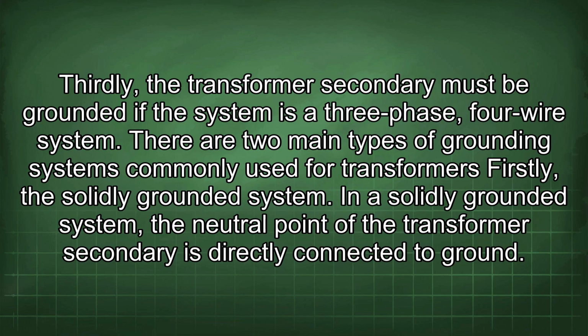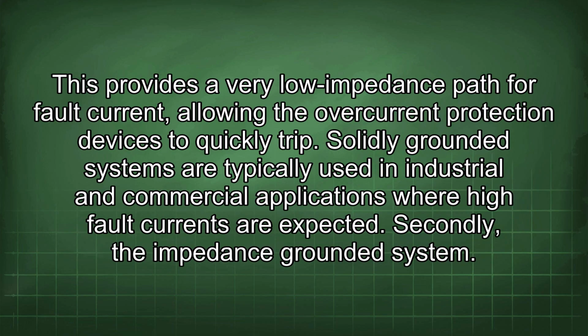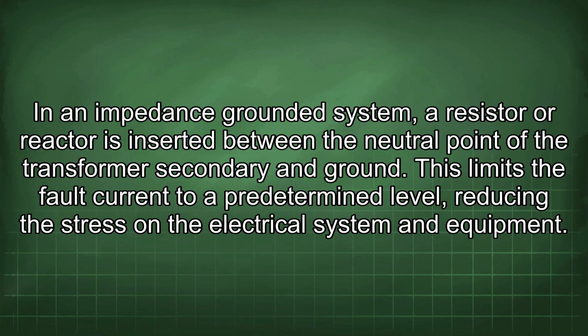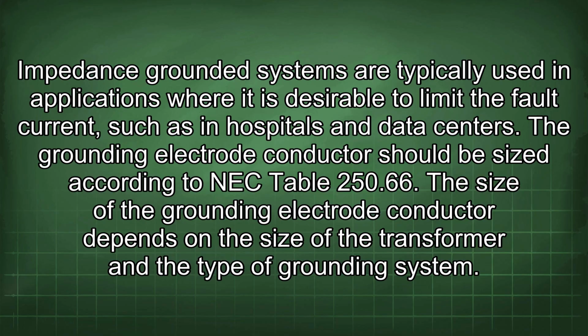In a solidly grounded system, the neutral point of the transformer secondary is directly connected to ground. This provides a very low impedance path for fault current, allowing the overcurrent protection devices to quickly trip. Solidly grounded systems are typically used in industrial and commercial applications where high fault currents are expected. Secondly, the impedance grounded system. In an impedance grounded system, a resistor or reactor is inserted between the neutral point of the transformer secondary and ground. This limits the fault current to a predetermined level, reducing the stress on the electrical system and equipment.